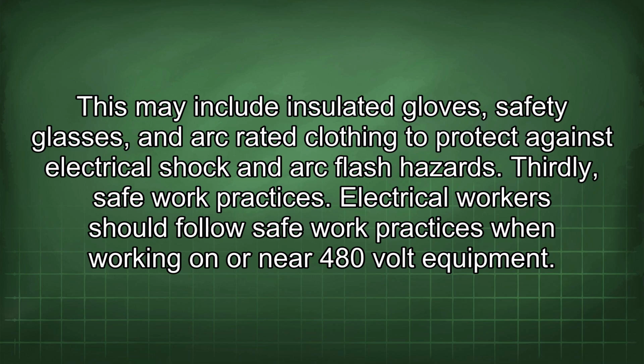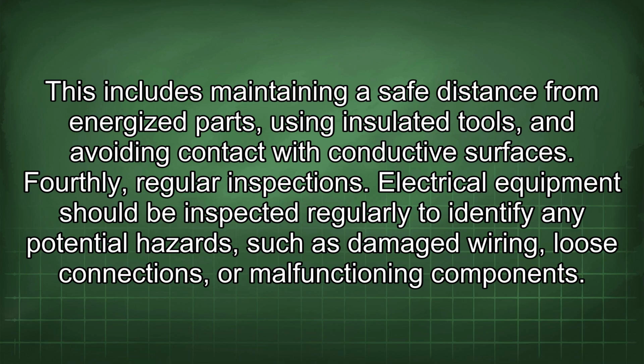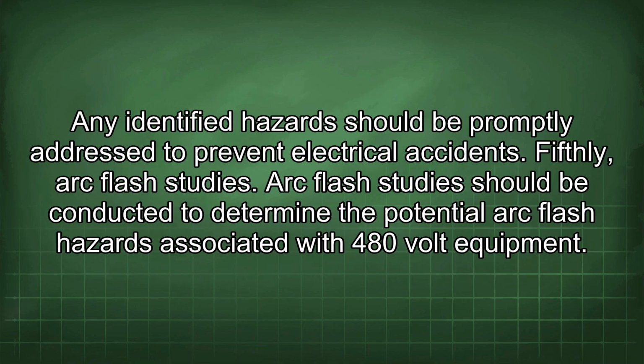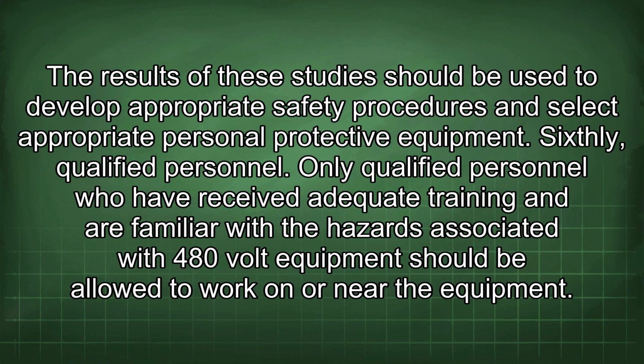Thirdly, safe work practices. Electrical workers should follow safe work practices when working on or near 480-volt equipment. This includes maintaining a safe distance from energized parts, using insulated tools, and avoiding contact with conductive surfaces. Fourthly, regular inspections. Electrical equipment should be inspected regularly to identify any potential hazards, such as damaged wiring, loose connections, or malfunctioning components. Any identified hazards should be promptly addressed to prevent electrical accidents. Fifthly, arc flash studies. Arc flash studies should be conducted to determine the potential arc flash hazards associated with 480-volt equipment. The results of these studies should be used to develop appropriate safety procedures and select appropriate personal protective equipment.